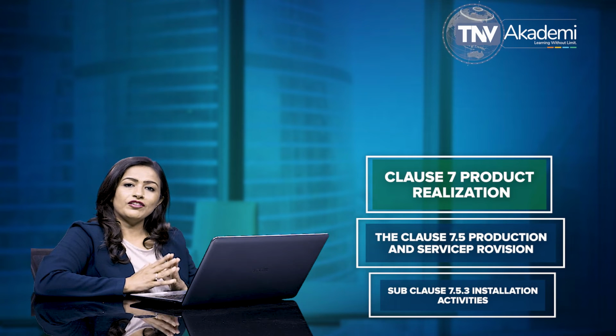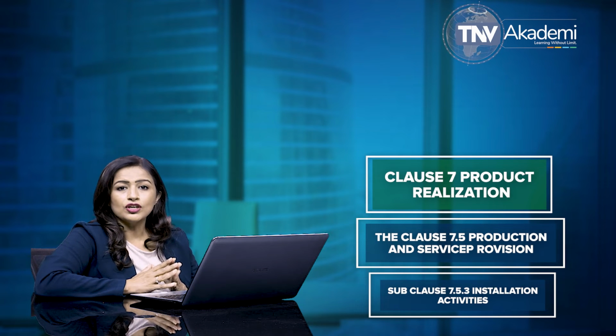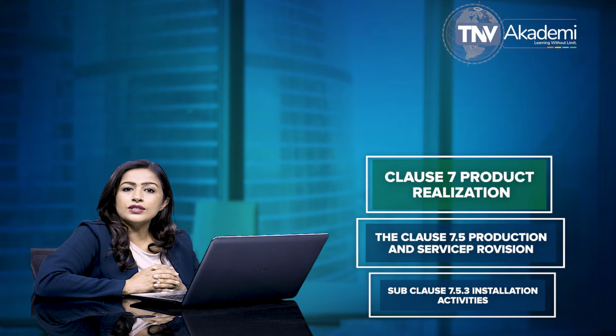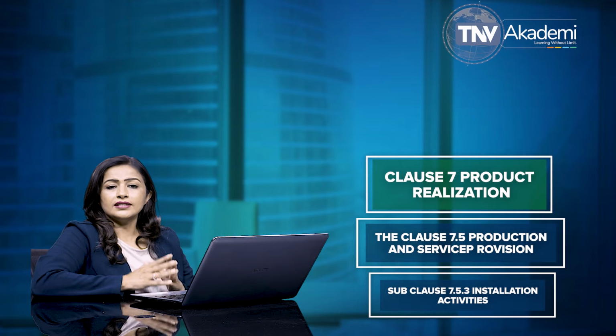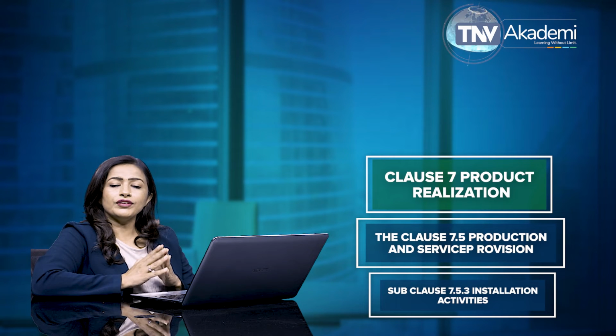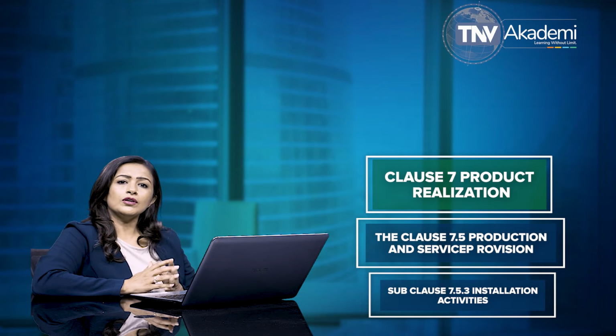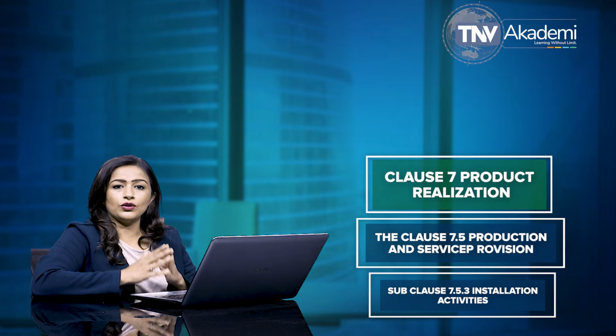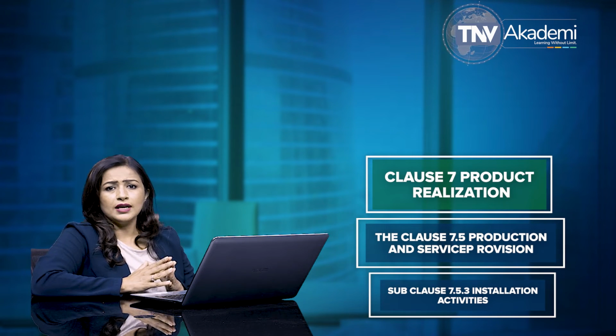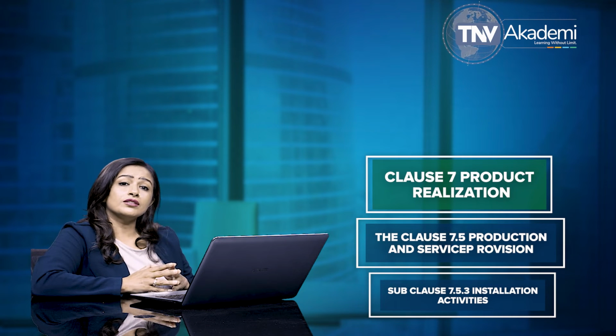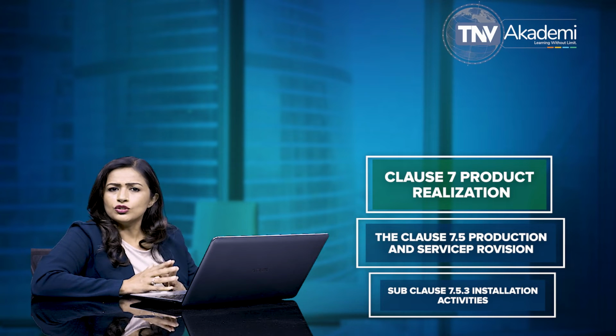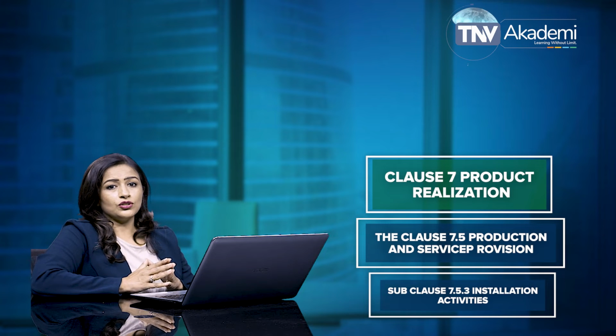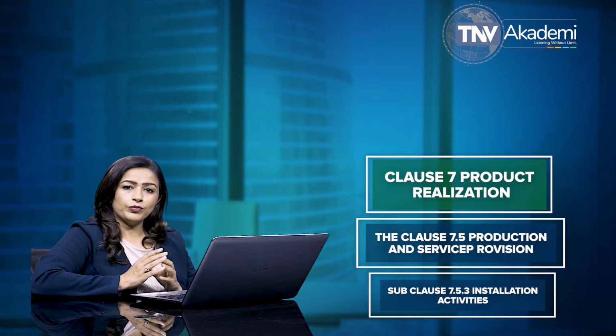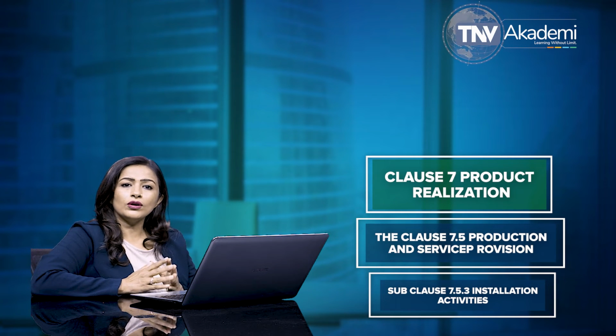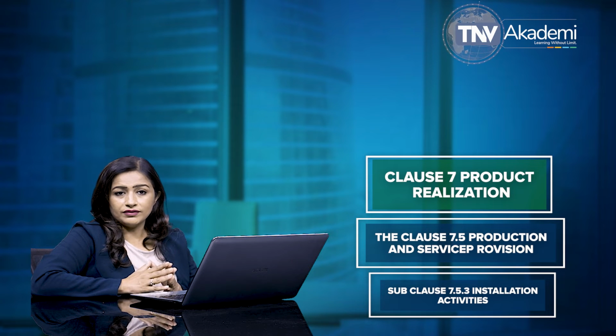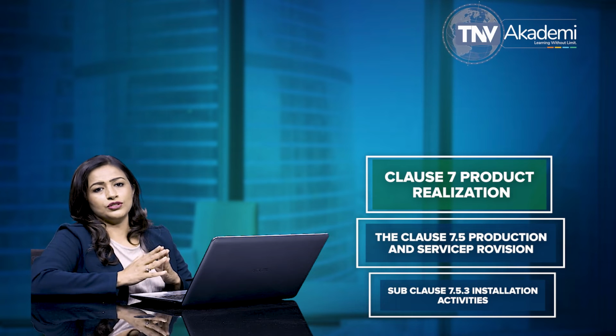This subclause 7.5.3 of ISO 13485/2016 says that the organization is required to document requirements for medical device installation and acceptance criteria for verification of installation as appropriate. The subclause specifies that the organization is required to provide documented requirements for medical device installation and verification of installation, if the agreed customer requirements allow installation of the medical device to be performed by an external party other than the organization or its supplier. Clause 7.5.3 further states that the organization or its supplier is required to maintain records of medical device installation and verification of installation performed.